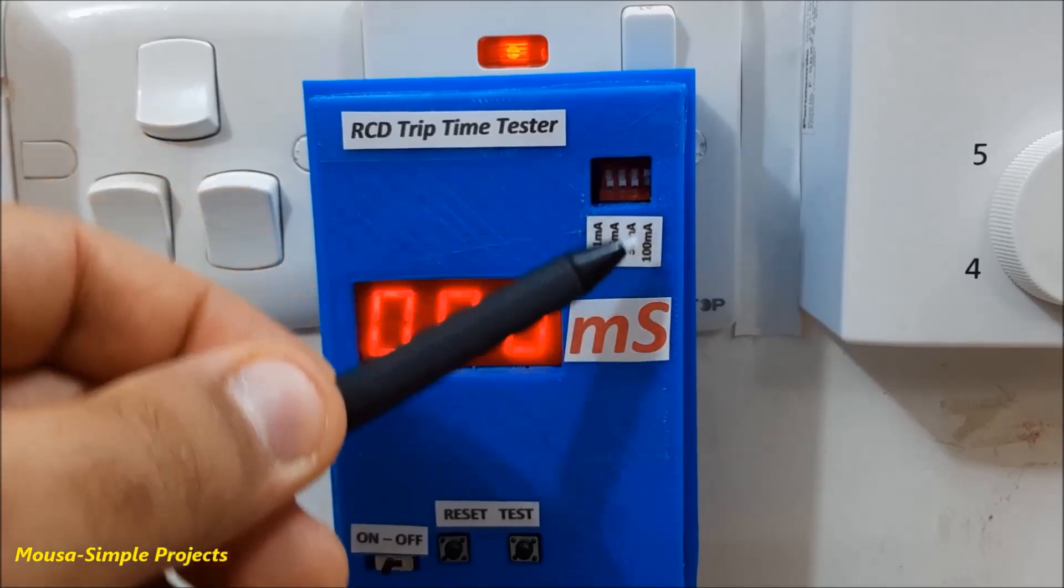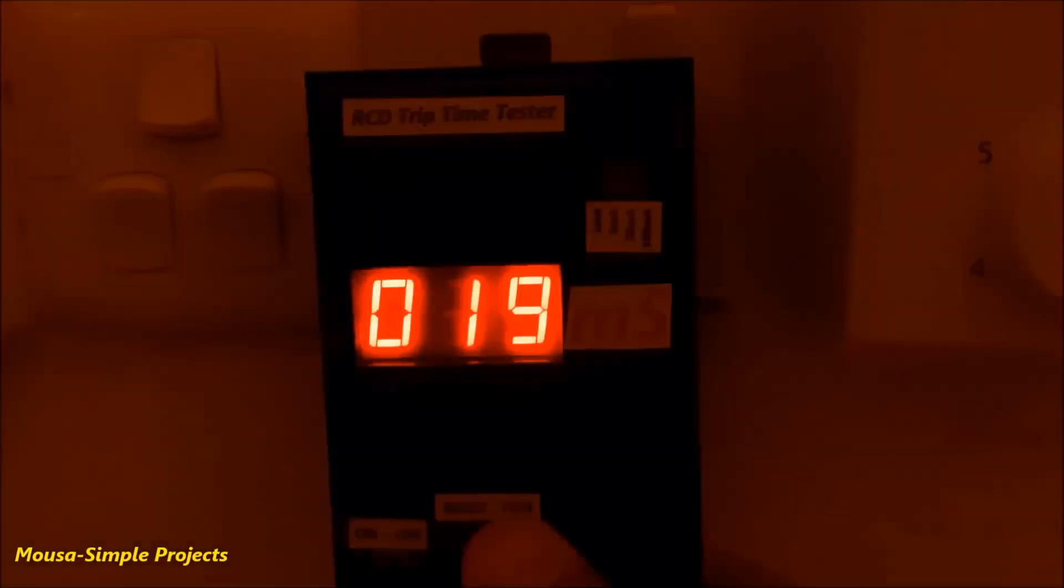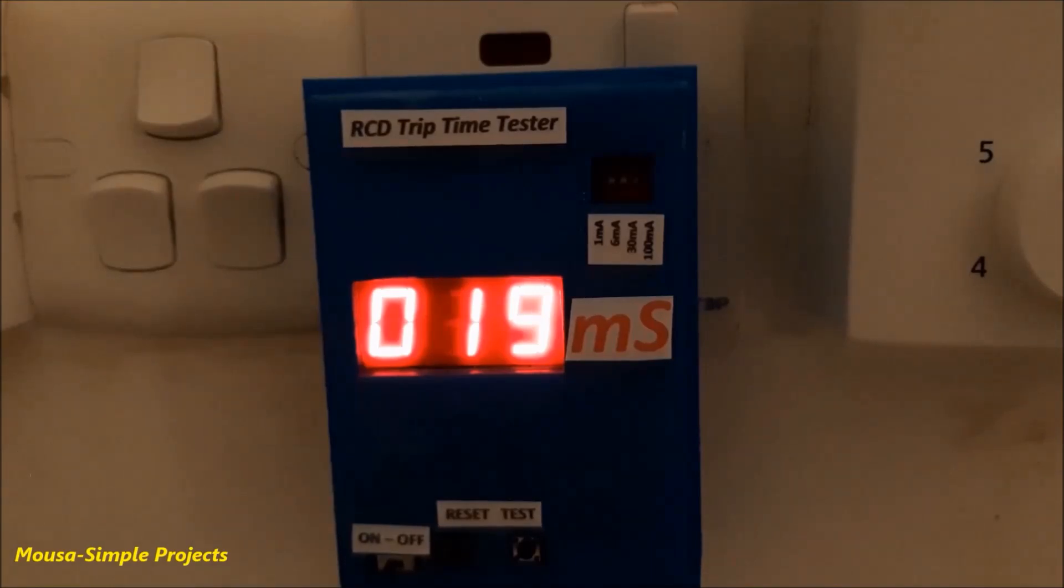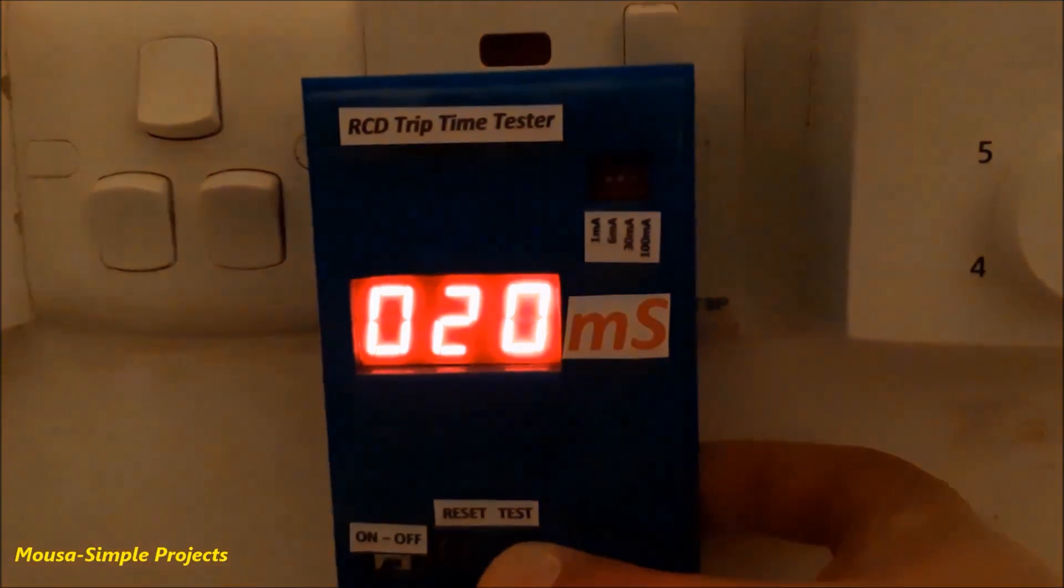Now let's try 100 mA of leakage current. This time, the RCD trips in 19 milliseconds, and one more time, 20 milliseconds.